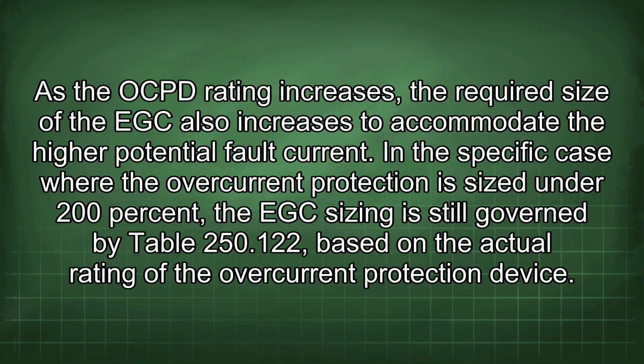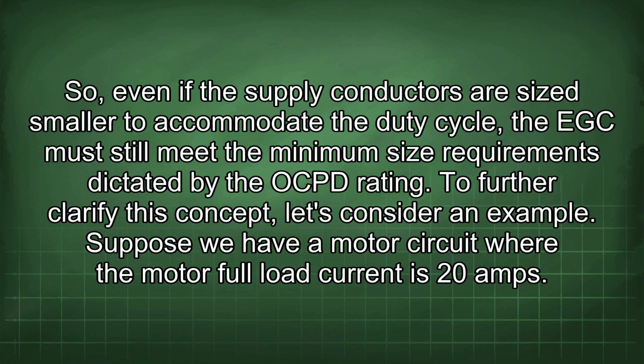In this specific case, where the overcurrent protection is sized under 200%, the EGC sizing is still governed by Table 250.122, based on the actual rating of the overcurrent protection device. So, even if the supply conductors are sized smaller to accommodate the duty cycle, the EGC must still meet the minimum size requirements dictated by the OCPD rating. To further clarify this concept, let's consider an example. Suppose we have a motor circuit where the motor full load current is 20 amps.